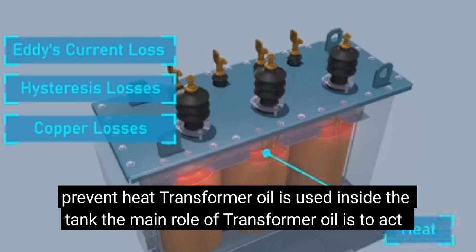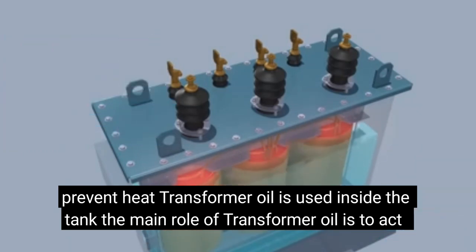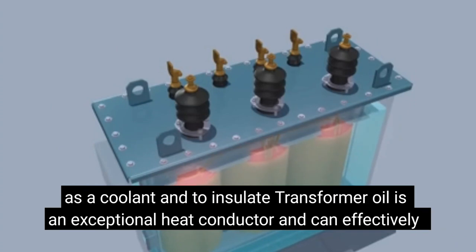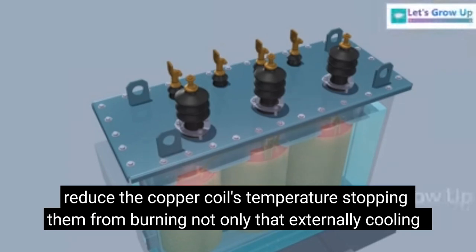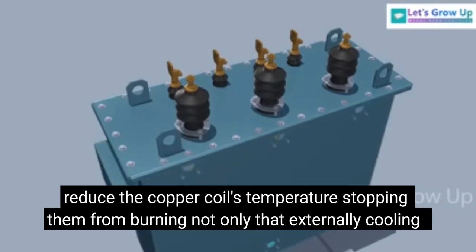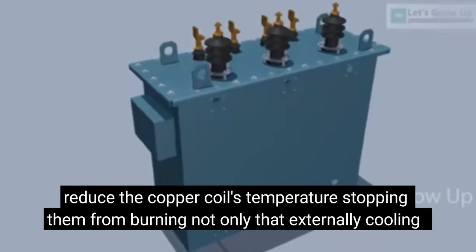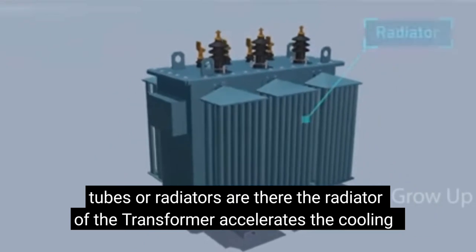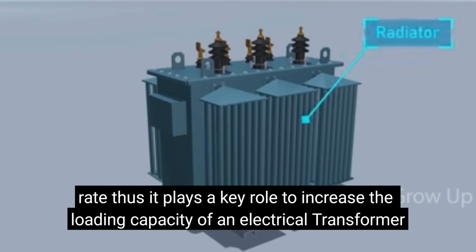To prevent heat, transformer oil is used inside the tank. The main role of transformer oil is to act as a coolant and to insulate. Transformer oil is an exceptional heat conductor, and can effectively reduce the copper coil's temperature, stopping them from burning. Not only that, external cooling tubes or radiators are there. The radiator of the transformer accelerates the cooling rate. Thus it plays a key role in increasing the loading capacity of an electrical transformer.